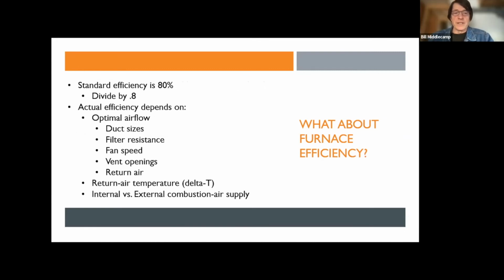What about furnace efficiency? Well, like I said, standard efficiency by law is 80%. But the actual efficiency of your furnace when it's installed in your home depends on how well your ductwork is designed and whether it's properly running. You know, if you've shut down a lot of vents, you're increasing the duct resistance and slowing the airflow, and airflow is key for heat exchangers. You have also resistance in the filter. Some people have gone out and replaced their filter with higher filtration numbers, and that creates more resistance. And if you don't take that into account, you can slow down the air flowing through the furnace and affect its efficiency. And if the filter is dirty, of course, is the fan speed at the proper speed, are the vents open, is the return air capable of flowing easily back to the furnace.